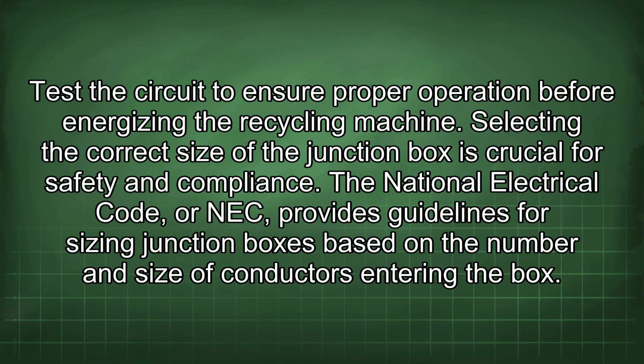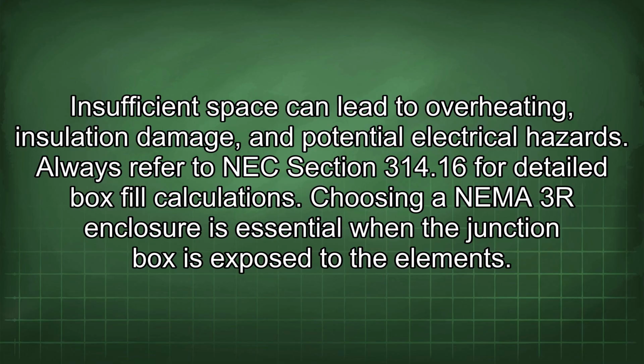Selecting the correct size of the junction box is crucial for safety and compliance. The National Electrical Code, or NEC, provides guidelines for sizing junction boxes based on the number and size of conductors entering the box. Insufficient space can lead to overheating, insulation damage, and potential electrical hazards. Always refer to NEC section 314.16 for detailed box fill calculations.